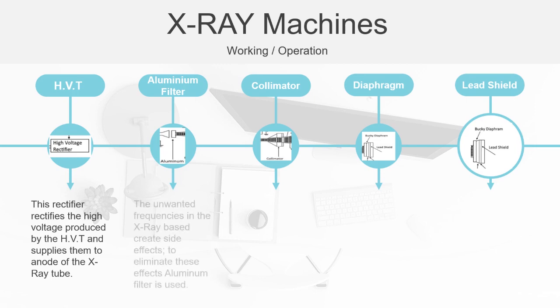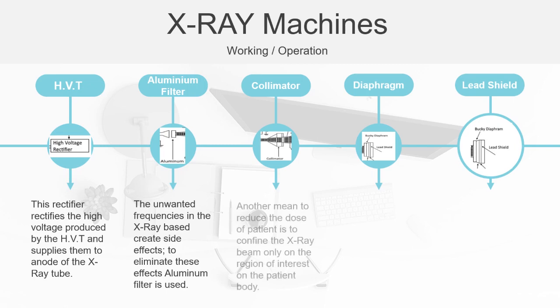The first element of the X-ray machine is the high voltage rectifier. This rectifier rectifies the high voltage produced by the high voltage transformer and supplies it to the anode of the X-ray tube where the X-rays are produced. These X-rays after being produced are passed through the aluminium filter. The unwanted frequencies in the X-ray beam create side effects; to eliminate these effects, an aluminium filter is used. The rays then pass through the collimator, whose purpose is to reduce the patient dosage by confining the X-rays only to the region of interest on the patient's body.